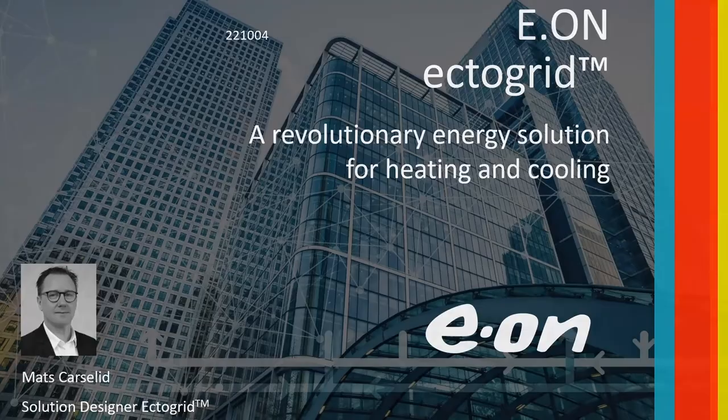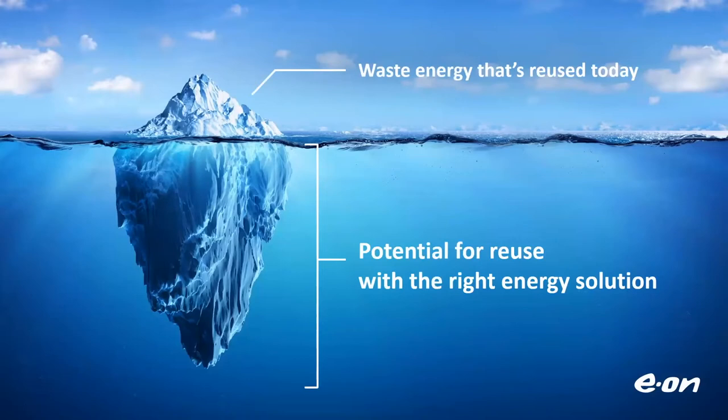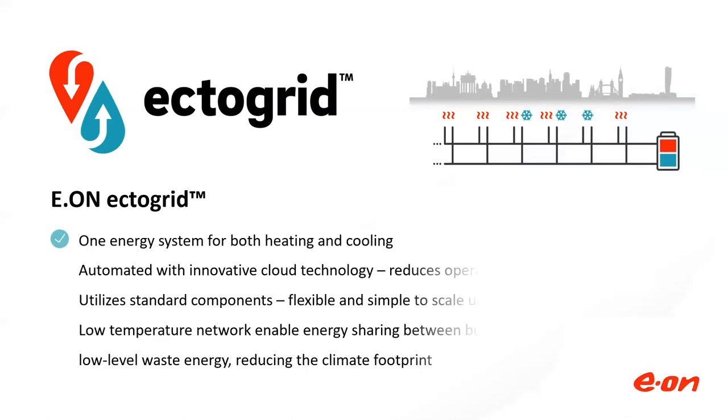So Ectogrid is all about sharing waste heat, taking care of what we typically take up through the roof with cooling towers or chillers or dry coolers. So it's all about reusing heat and cold. Ectogrid is one system. It's a two-pipe system for both heating and cooling. In traditional district heating, district cooling, you need four pipes. Here we have two pipes.